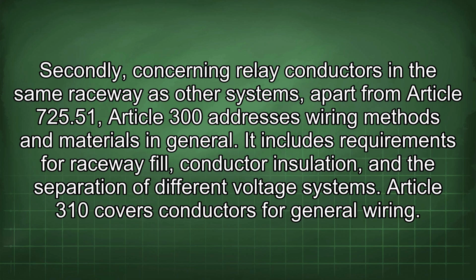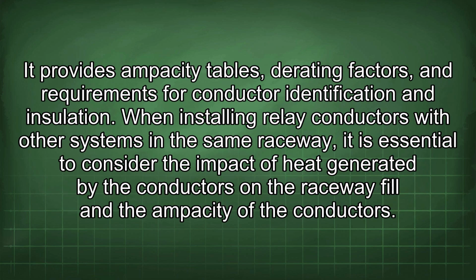Secondly, concerning relay conductors in the same raceway as other systems, apart from Article 725.51, Article 300 addresses wiring methods and materials in general. It includes requirements for raceway fill, conductor insulation, and the separation of different voltage systems. Article 310 covers conductors for general wiring. It provides ampacity tables, derating factors, and requirements for conductor identification and insulation.